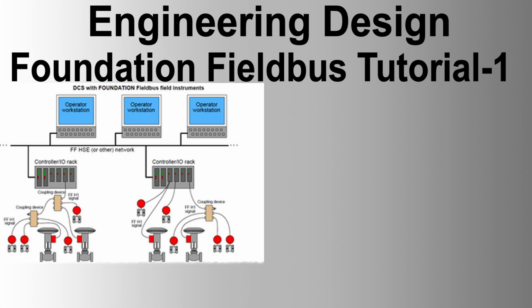Physical layer. 31.25 kbps physical layer. Physical layer is the most common since IEC and ISA approved it in 1992. This textbook explains only wire medium, but optical fiber can be used as an alternative. Though 31.25 kbps sounds slow compared with the latest telecommunication technologies, it is necessary to replace traditional 4 to 20 milliamps analog transmissions. It is intended to apply to field devices for various environments of industries.